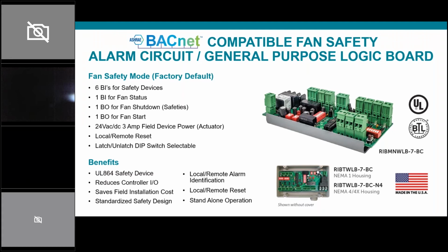Additionally, each input can be overridden using local dip switches, which can be used to latch any of the 6 binary inputs. If any of the inputs are latched and there is a fault in the input, the master relay will be energized again by both clearing the fault and clearing the latch. And then you can reset on the board by cycling power or over BACnet.